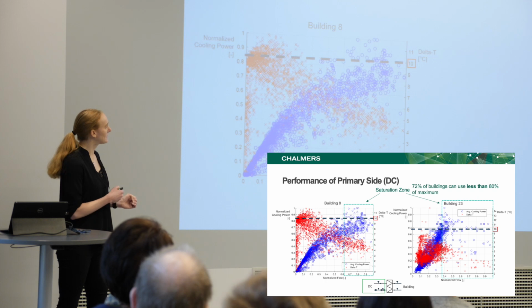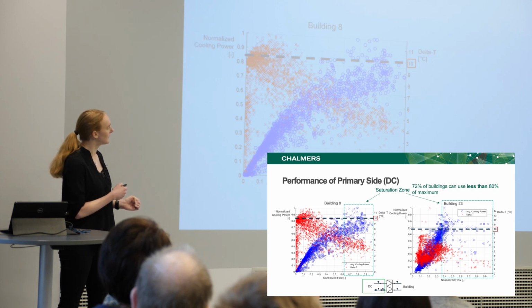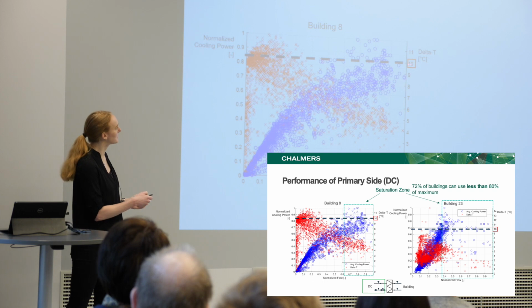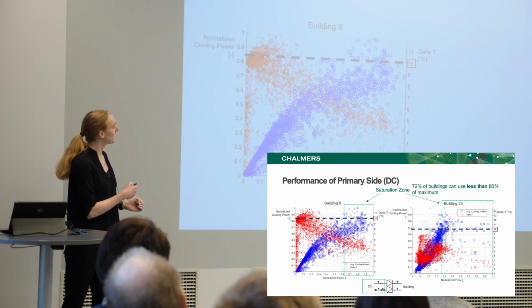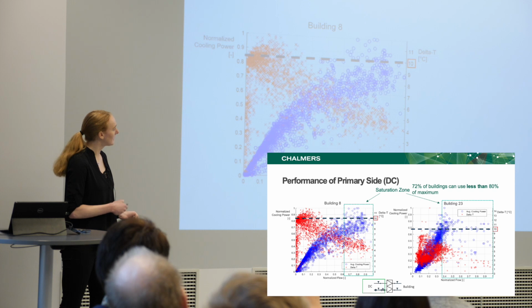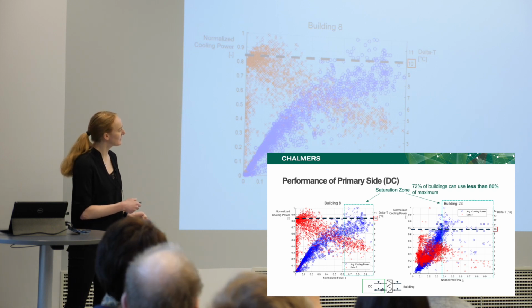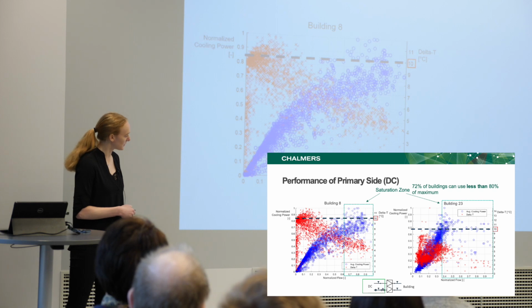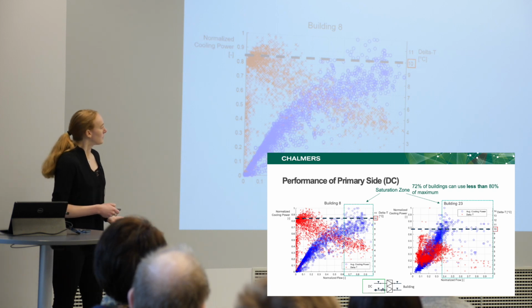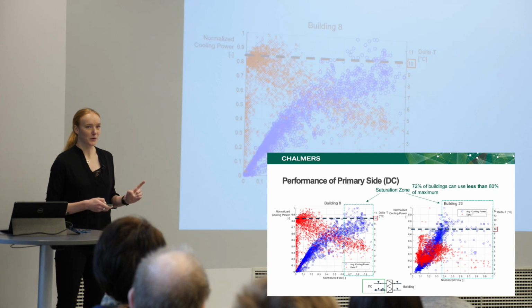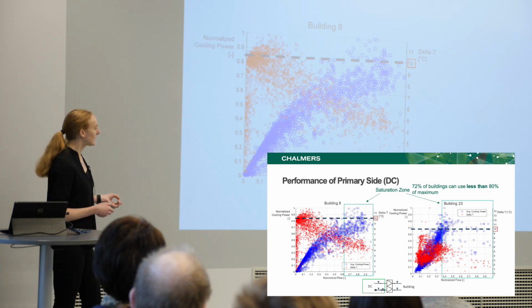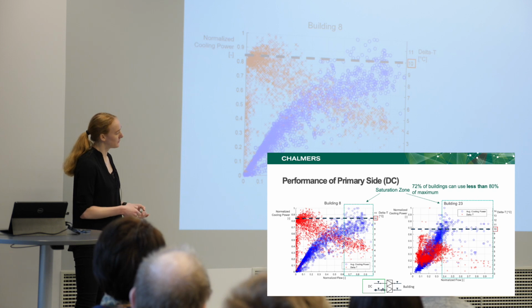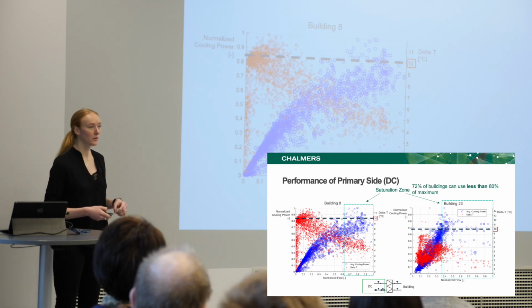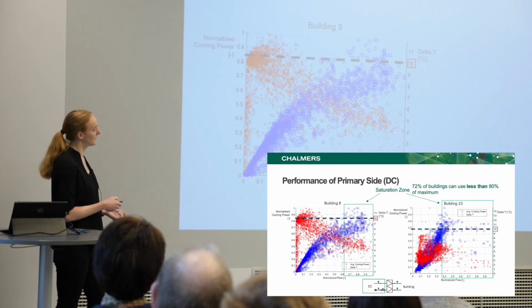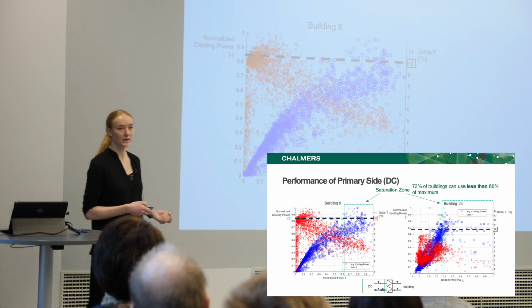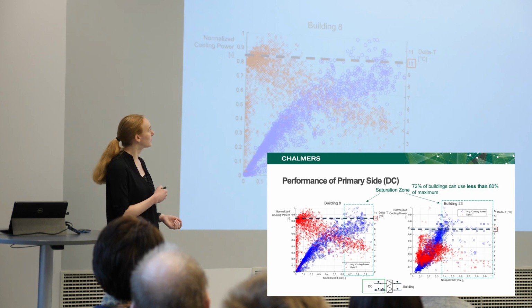However, in this building, you can see that the delta T is 10 degrees, which is illustrated by this line, when the flow is low. And then it just slowly drops for an increased flow rate. That was one trend observed, which was the most common. And that says that the flow on the building side is variable, so this is the behavior of delta T: it's going to drop when the flow increases, and it will be high when the flow is low.